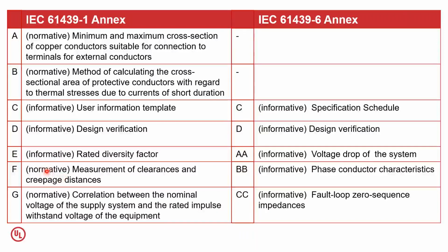Then we run across many of the normative requirements, which are mandatory. So in order to meet this standard, you will mandatorily have to make sure the clearance and creepage distances meet the requirements in the standard. And then you mandatorily need to declare the impulse value depending on your need, and then the testing is performed accordingly, and that's why this is made normative. Normative means mandatory, informative means you have certain flexibility to choose depending on your need.